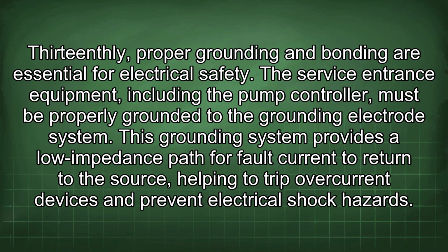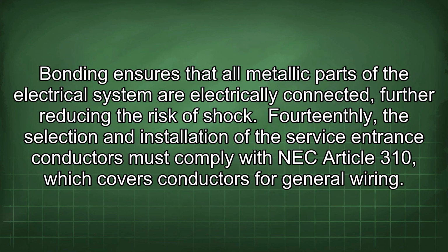The service entrance equipment, including the pump controller, must be properly grounded to the grounding electrode system. This grounding system provides a low impedance path for fault current to return to the source, helping to trip overcurrent devices and prevent electrical shock hazards. Bonding ensures that all metallic parts of the electrical system are electrically connected, further reducing the risk of shock.